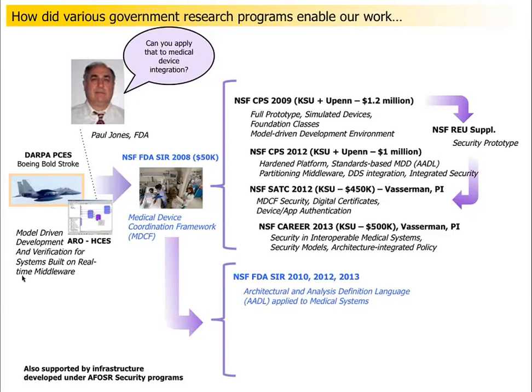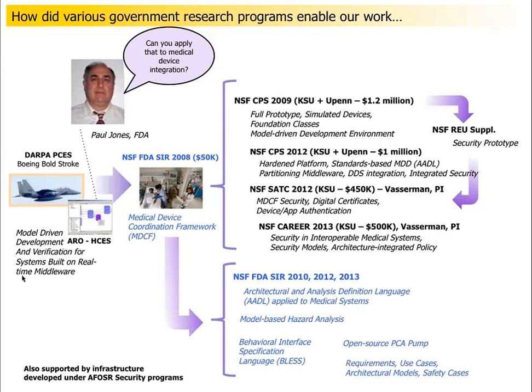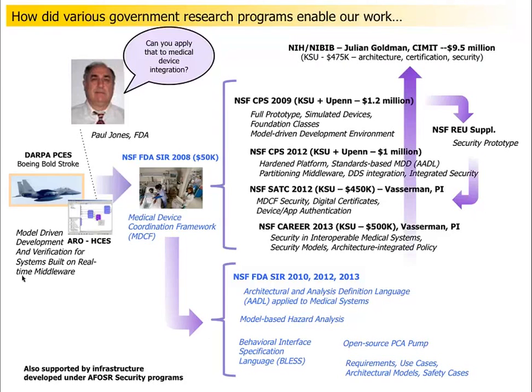And we've been able to say, well, what would it mean to use the model-driven development like AADL in the certified medical space? How can we do things like model-based hazard analysis? How can we define formal interface specification languages that capture the type of behaviors, including timing information, quality of service, and so forth, and have those be a part of the artifacts that are considered in a regulatory submission? There's also a number of other things that we've done, building out things like requirements, methodologies, use cases, architectural models, and so forth, and safety cases in this context that's been enabled by this FDA Scholar in Residence money.